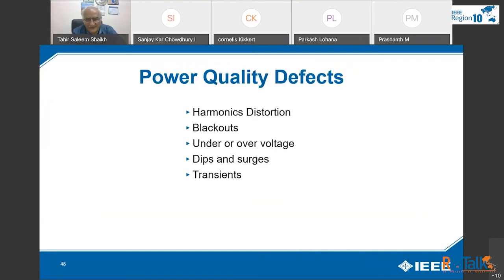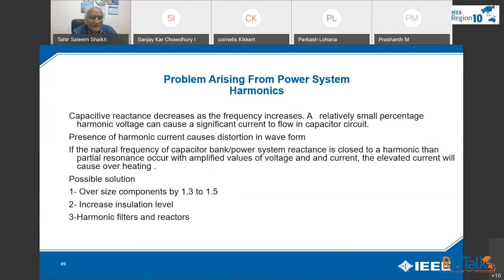So this we have discussed: harmonic distortion, blackouts, under and over voltage, dips and surges, and transients. Now I come to the different solutions. For capacitors, the capacitive reactance decreases as the frequency increases. A relatively small percentage of harmonic voltage can cause a significant current to flow in capacitor circuits. Presence of harmonic current causes distortion in the waveform. If the natural frequency of a capacitor bank and power system reactance is close to a harmonic, then parallel resonance occurs with amplified values of voltage and current. The elevated current will cause overheating.